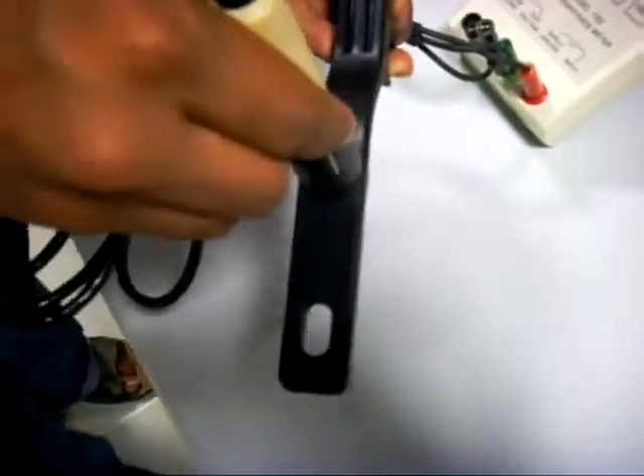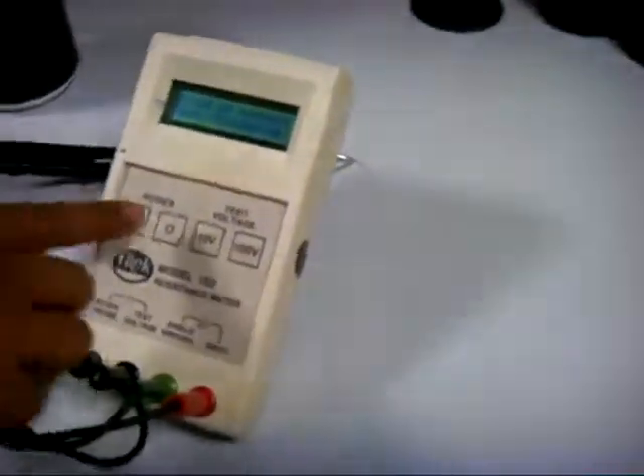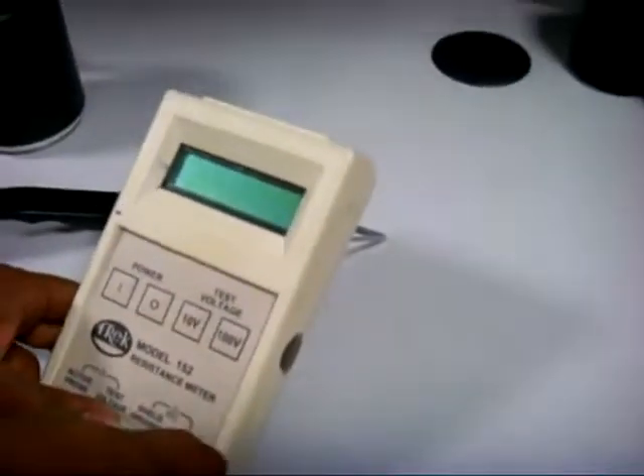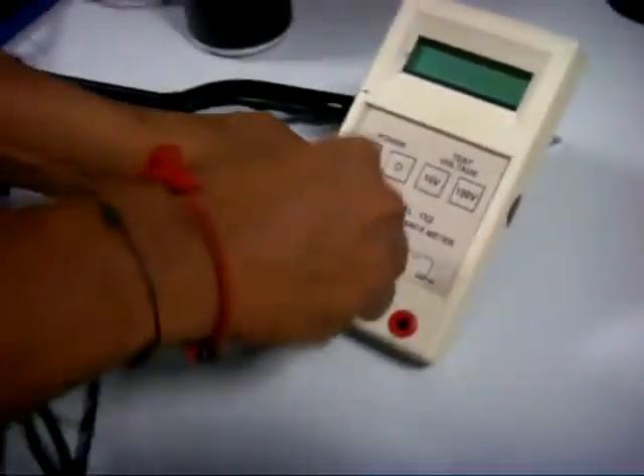Switch on the instrument. Okay, since this is a conductive material, we are checking at the 100 volt range. I have to place the mini probe on the surface. We are getting 6.5 into 10 power 4 ohms. Switch off. Next we are going to test the volume resistance of that bag.